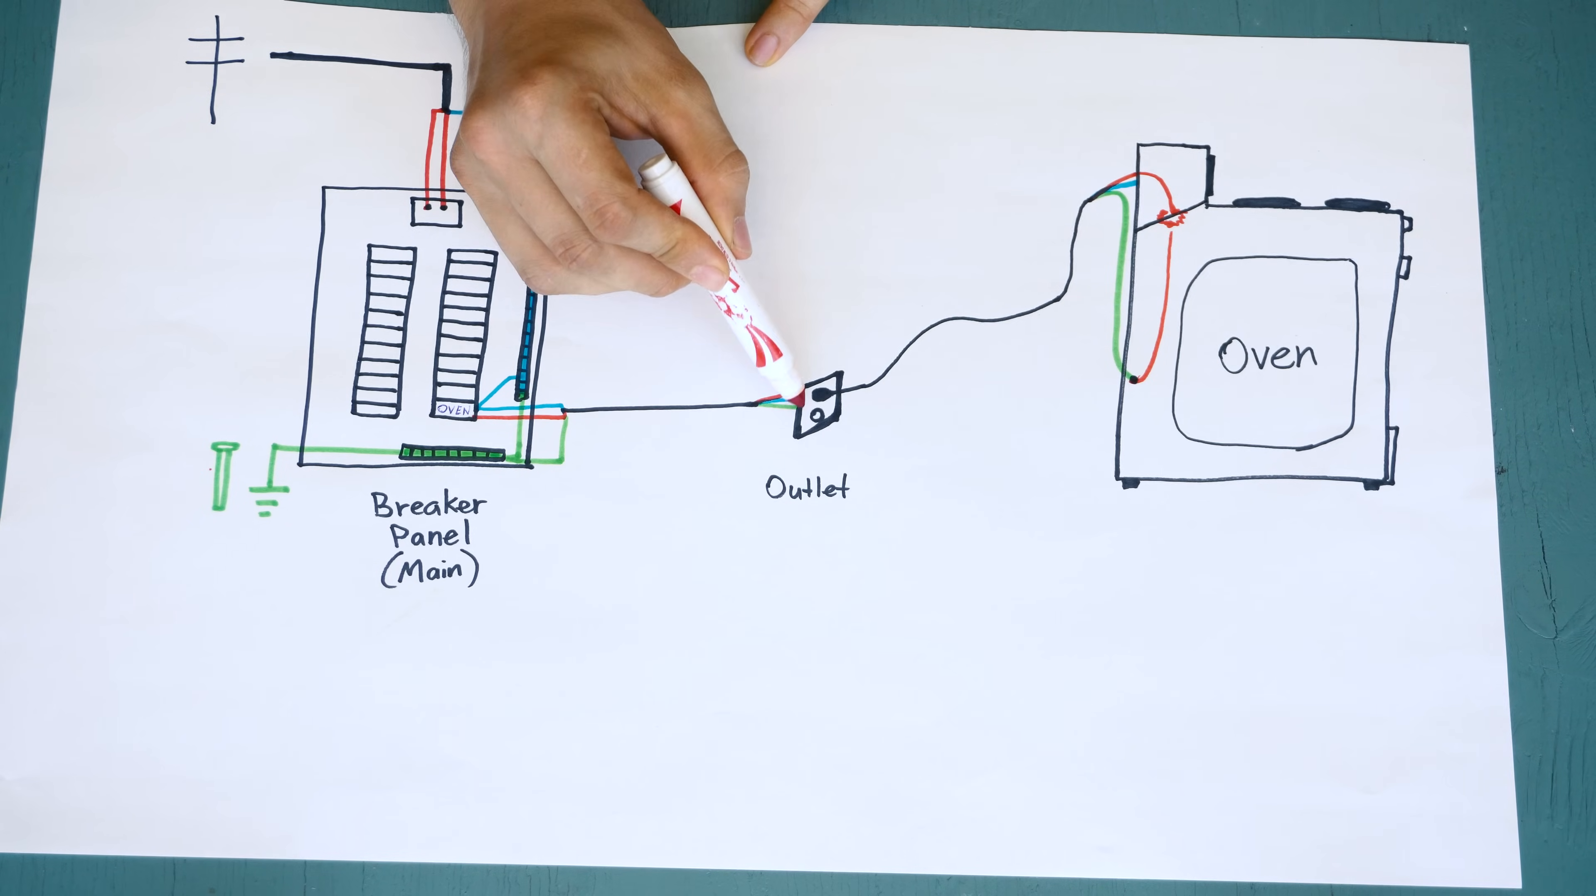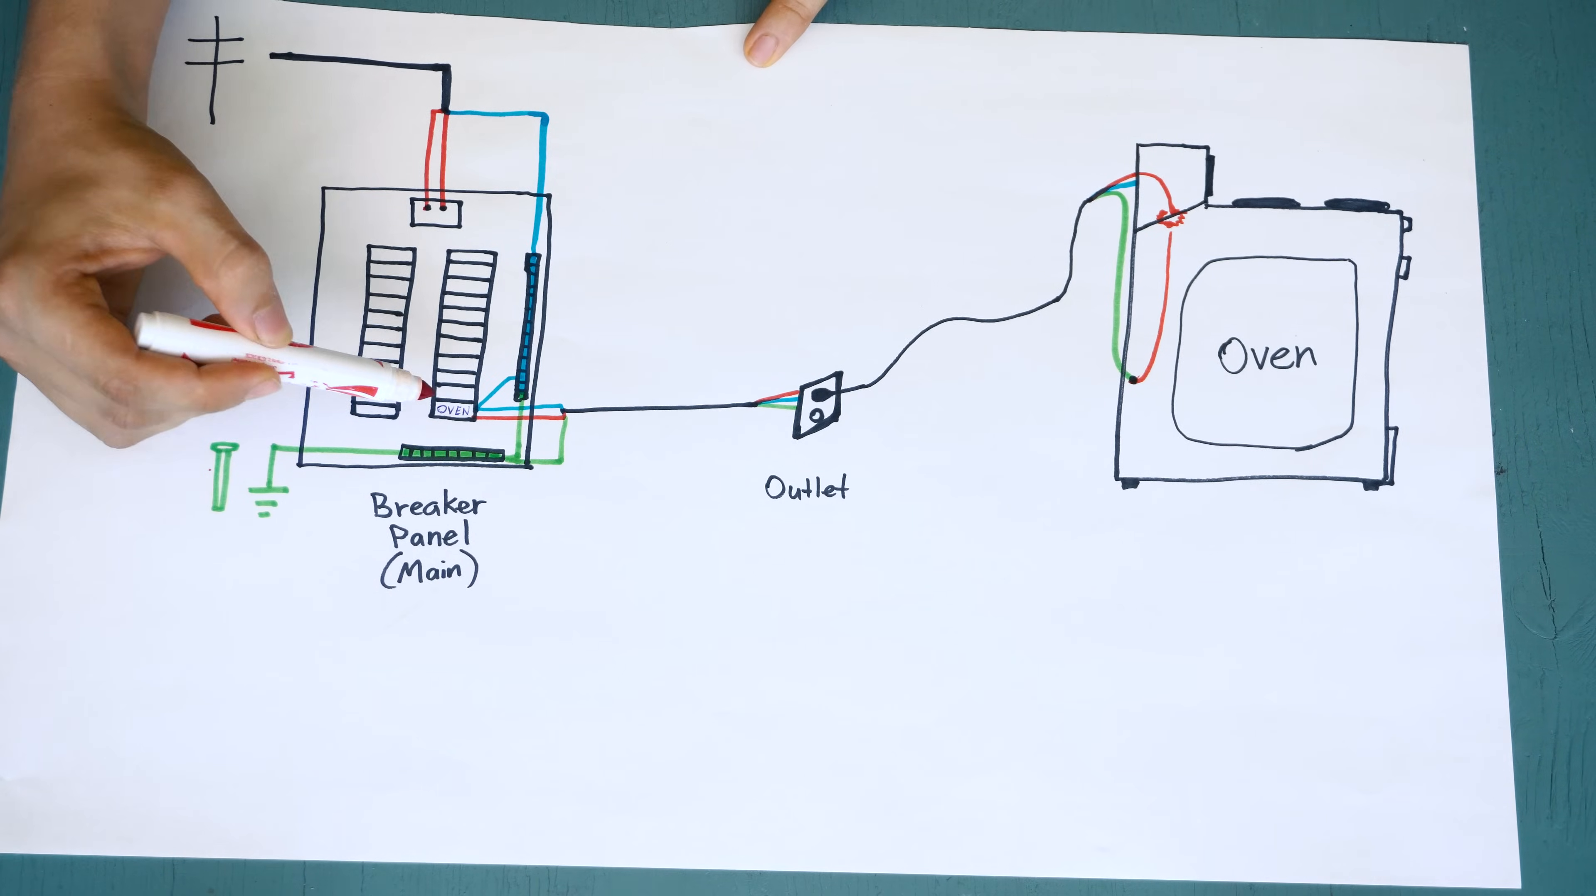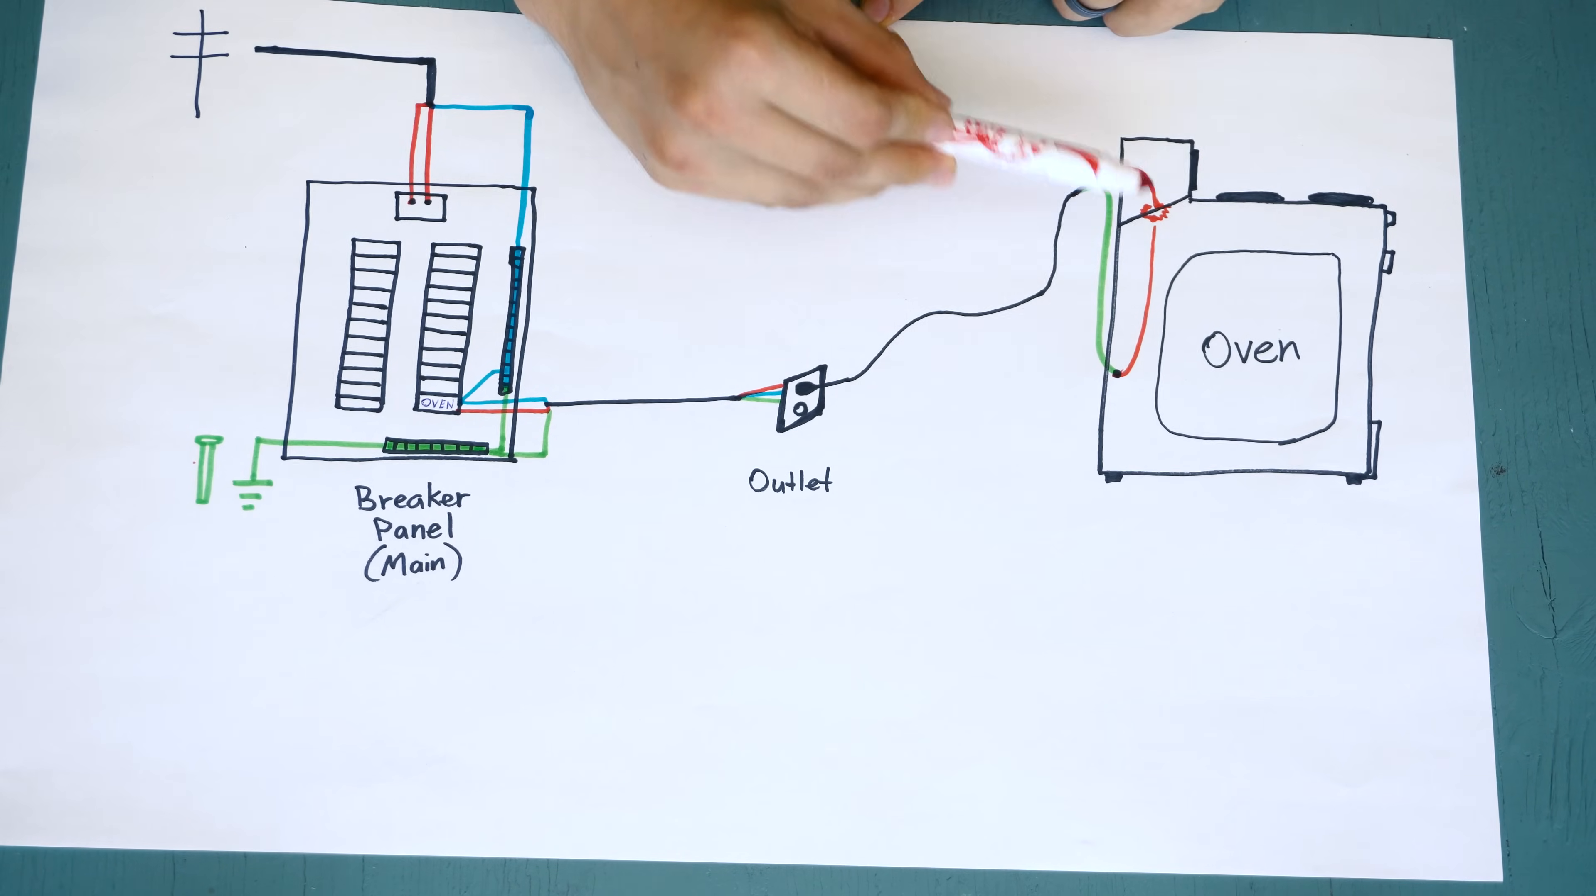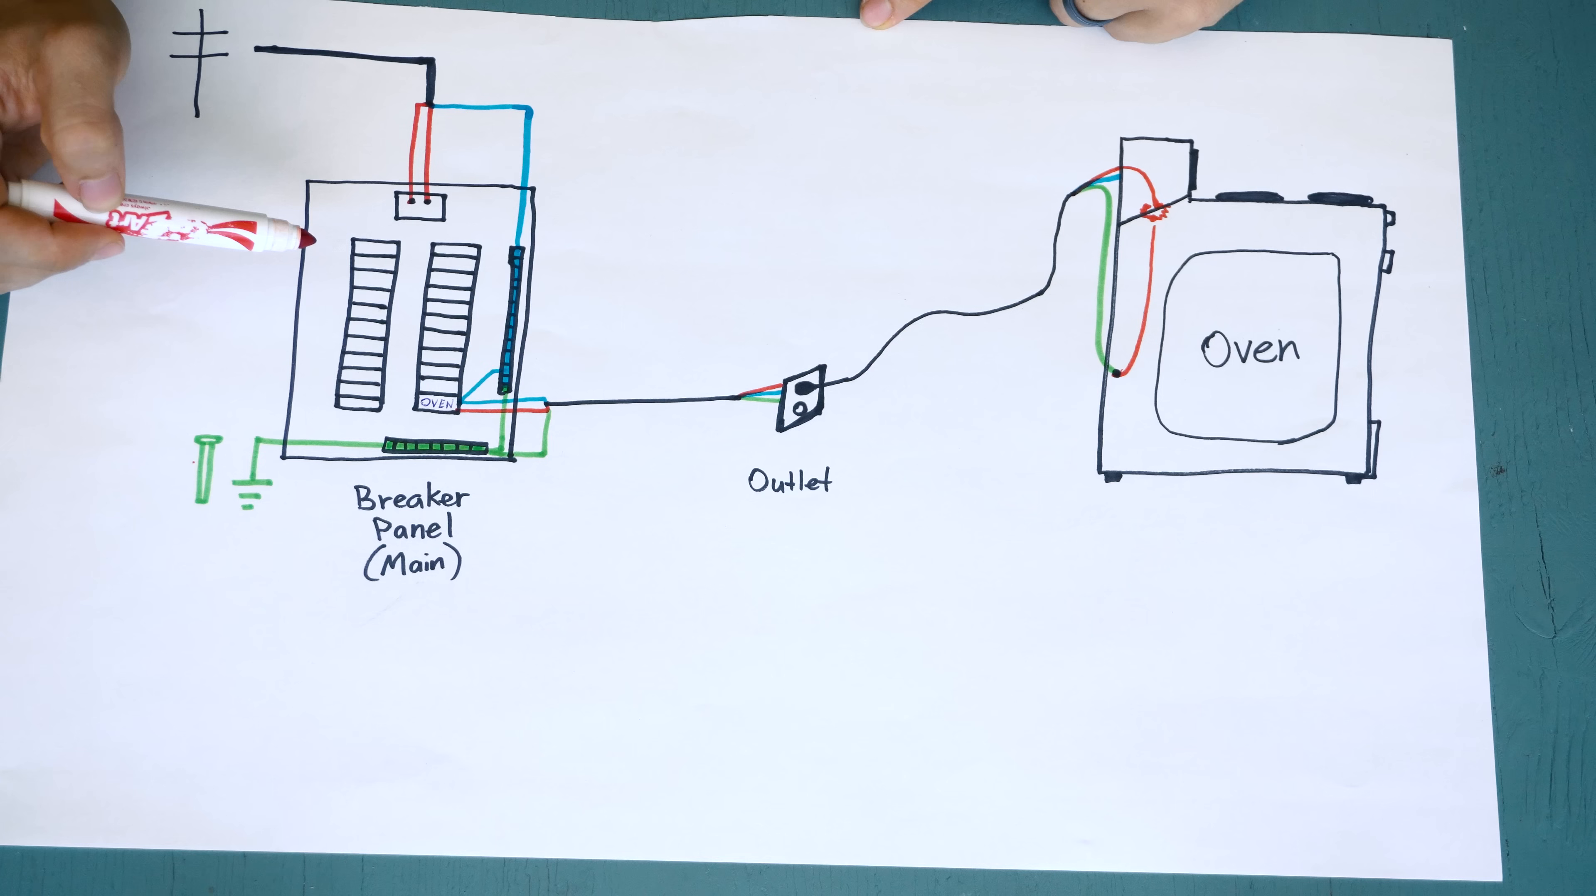So if it is shorting out right here, electricity will choose the path of lower resistance, which would be the ground, and it'll go back and hopefully once again overload the circuit, or if there's a GFI in here, trip that and turn the power off. So in summary, the ground is a safety that hopefully will never get used. Normal operation does not involve the ground, but when something does go weird, like a mouse chewing through a wire and the whole oven gets energized, that's when the ground kicks in and hopefully turns that breaker off real fast.